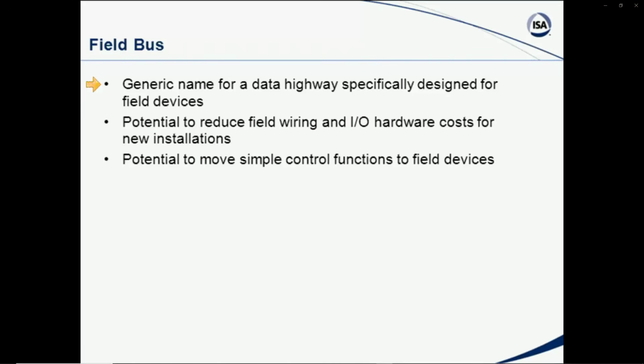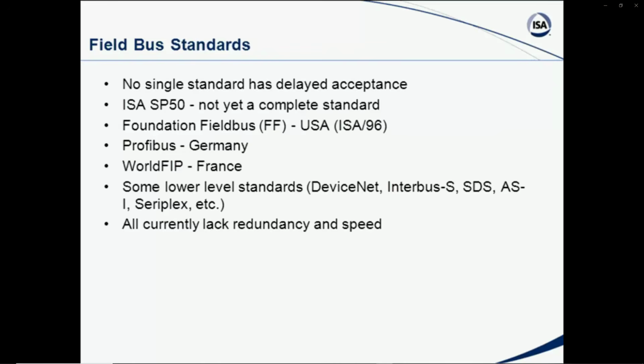It's a data highway, and you have various field devices that are hung off of, if you will, this data highway. And with this fieldbus, information is bused back inside to our control center and back out to our control devices. By doing it this way, there's tremendous potential for reducing the field wiring and input-output hardware cost, and actually going even further with true distributed control using fieldbus. You have the potential to actually move the control functions out to the field devices. Locate that actually in the transmitter, locate that control function actually in that smart valve package. Some people are doing that rather extensively. Others are doing it on a cautious basis, but we need to be aware of that in case some sort of a question did come up.